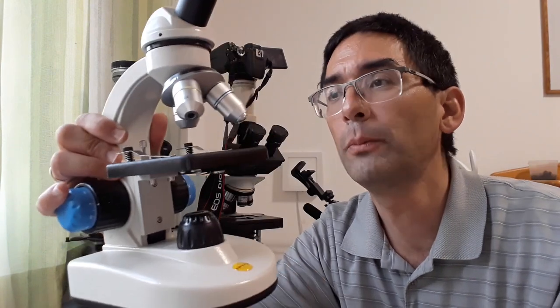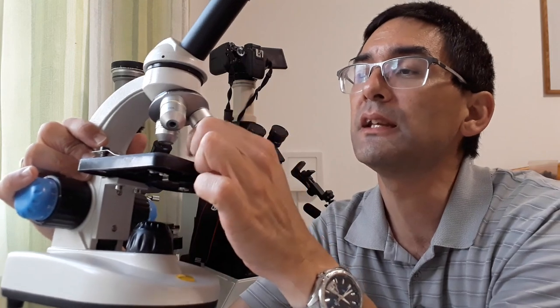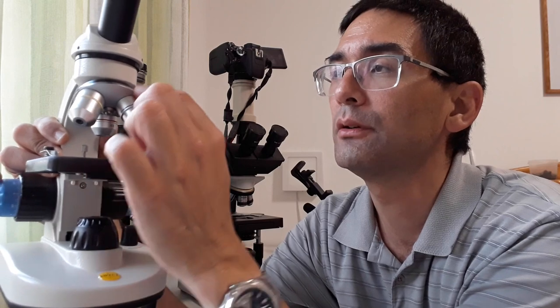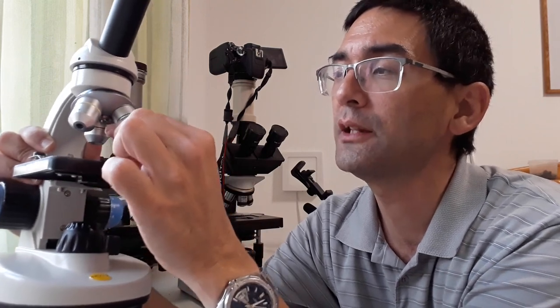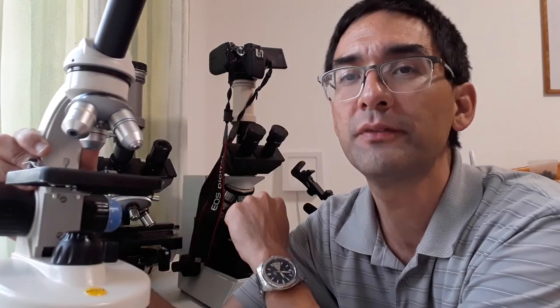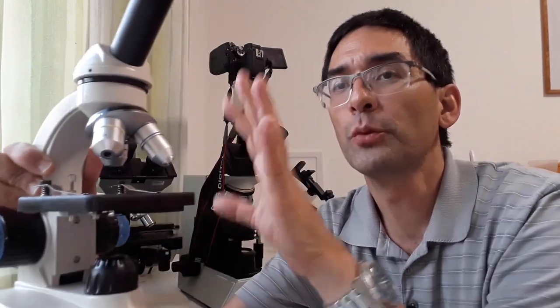But as a matter of fact many of them actually have the 160 millimeter objective and it's basically standardized now. There are certain very low-cost microscopes like for example I've got one here, it's a National Opticals or also the Swift S110 microscope and if you actually now look at these objectives here you see that they basically are a little bit smaller and they basically are not 160 millimeter DIN standard objectives and therefore they are not compatible.